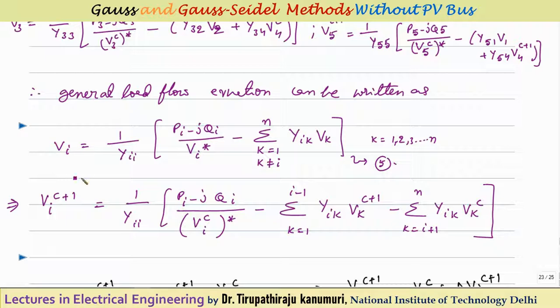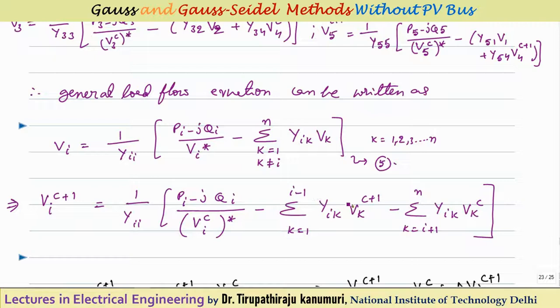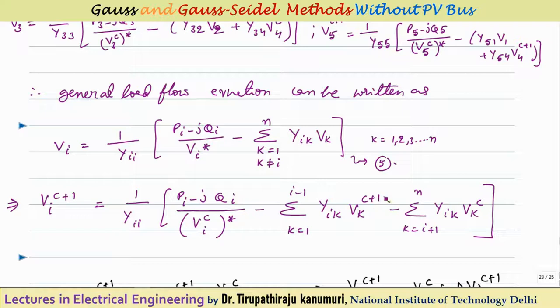The generalized Gauss-Seidel voltage update equation is: Vi(C+1) = (1/Yii)·{(Pi−jQi)/Vi(C)* − Σ(k=1 to i−1) Yik·Vk(C+1) − Σ(k=i+1 to n) Yik·Vk(C)}. Buses 1 to i−1 have already been updated in the current iteration so we use Vk(C+1), while buses i+1 to n have not yet been updated so we use Vk(C).